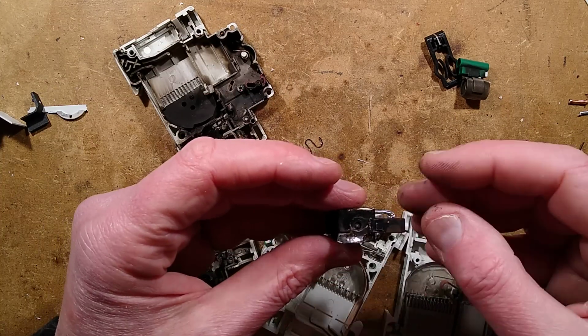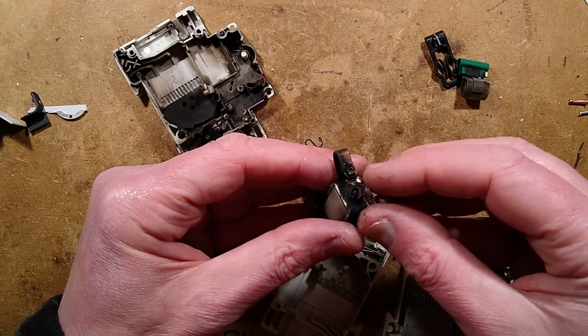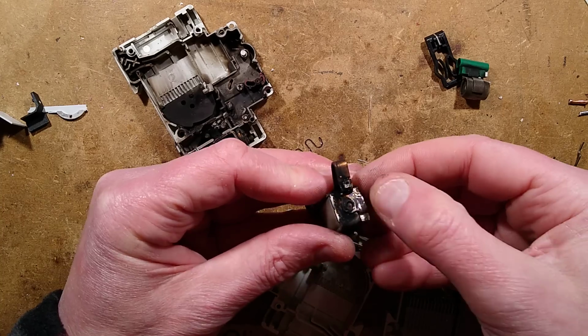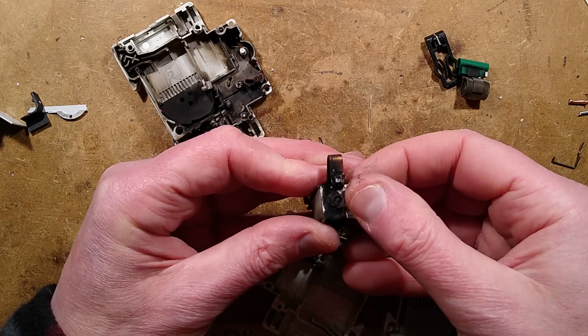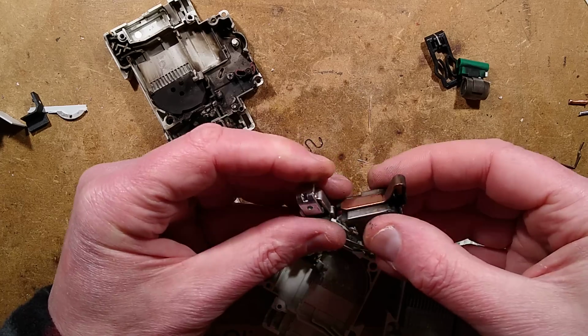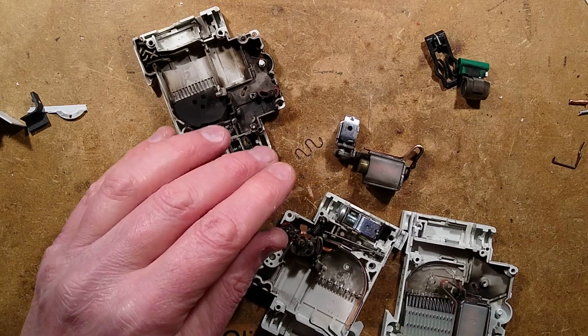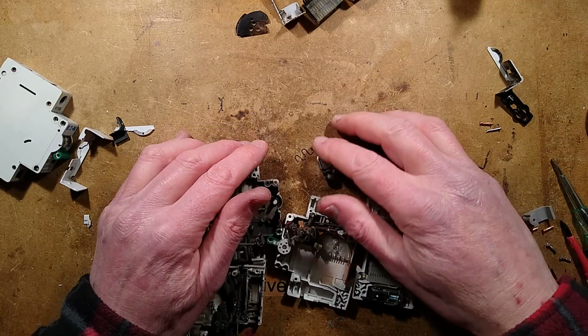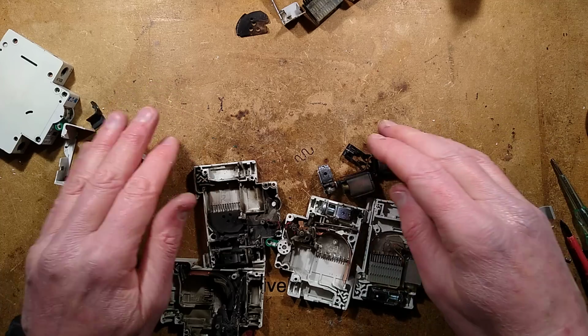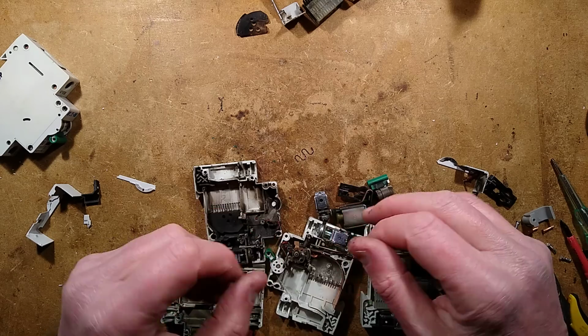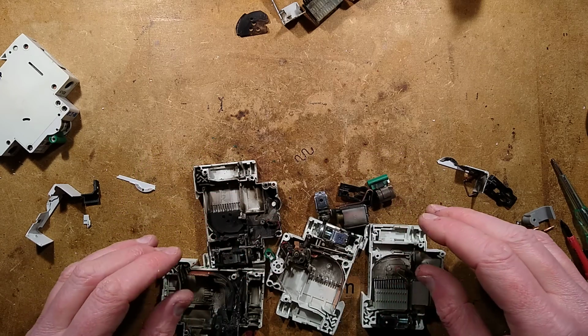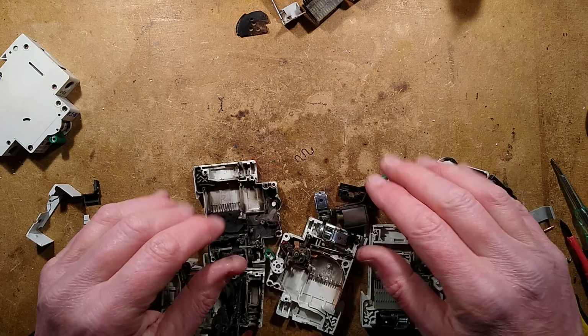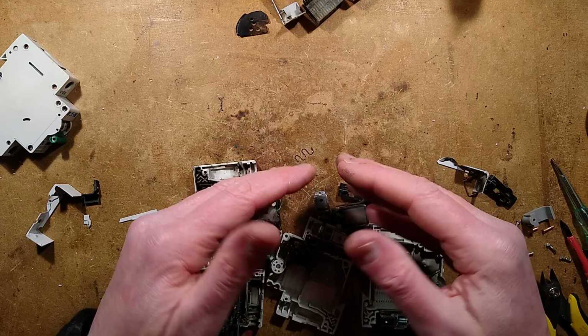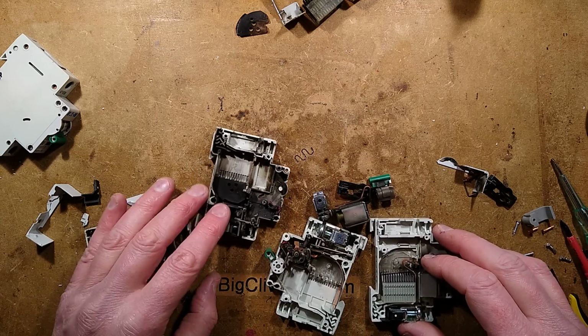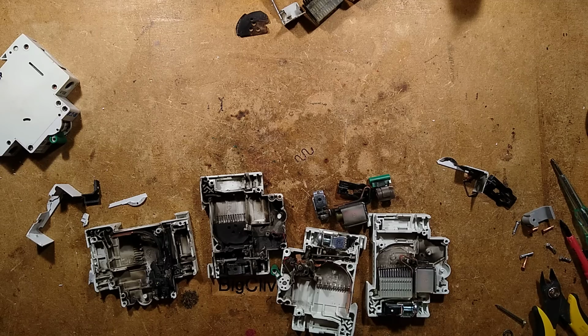There's the contact plate, and it just looks like it tried to break the circuit, but arc flash - you can see the weld here where the sparks ran onto that, and that's where it's flashed over. The moral of the story is that if you're resetting a circuit breaker into a suspect fault, it might be worth getting thick gloves on for an extra layer of protection. It might not protect you completely, but it may just in that one instant protect your fingers from burns if flames come out the front of the panel. But there we have it, a well and truly exploded circuit breaker from one of those irksome intermittent faults that does occasionally occur.